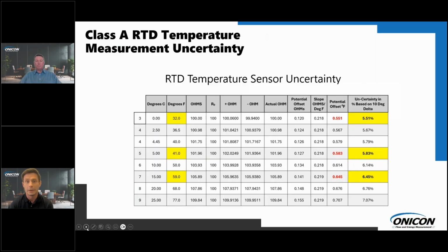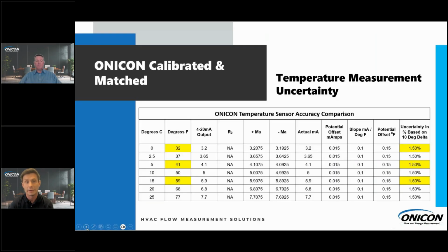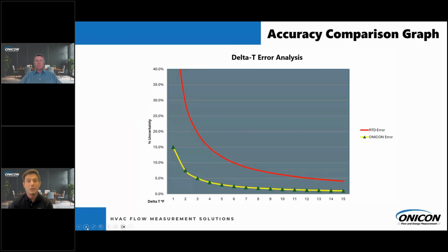When you compare that to our ONICON match paired semiconductor solid state temperature sensors, you can see in the table the exact same temperatures, but when you look to the right, our potential offset is consistent across the board. And so is our error of accuracy across that 10-degree delta. It remains at 1.5%. And when you graph this out, you can see the difference.